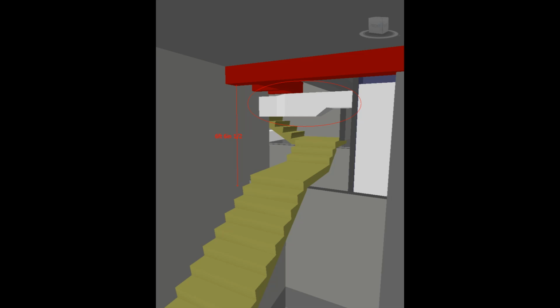Then a soft clash is going to be a bit more subtle. That's when you have an object that has spatial dependencies around it. A good example of that is a piece of HVAC equipment that needs to have a certain clearance so that the door can open on it and the filter can be changed.